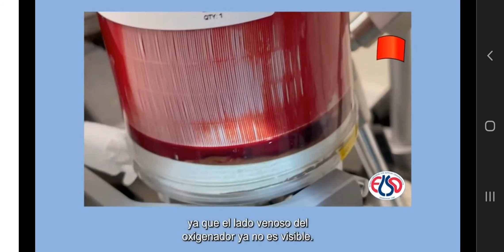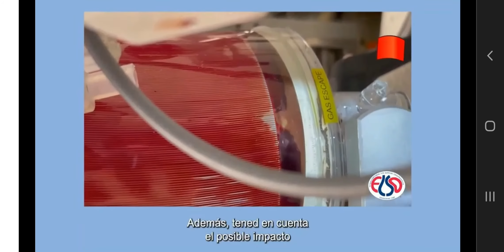With devices integrating the centrifugal pump and the membrane lung in a single block, inspection of the venous side of the oxygenator is not feasible anymore. Also consider the eventual impact on blood cells, with increasing signs of hemolysis and no other evident explanation, and consider the eventual impact on coagulation due to consumption coagulopathy, with signs of disseminated intravascular coagulation and bleeding. Again, with no other evident explanation.